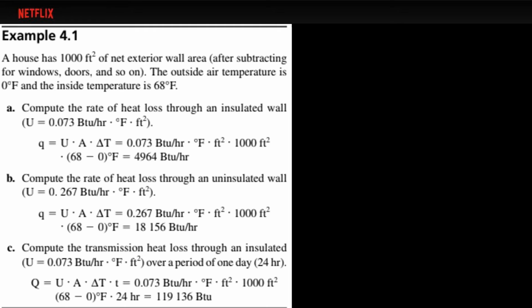So, example, a house has 1,000 feet squared of net exterior wall area, after subtracting the windows, doors, and so on. The outside air temperature is 0 Fahrenheit and the inside temperature is 68 Fahrenheit. So A, compute the rate of heat loss through the insulated wall. So now, the formula from earlier is on the last slide. It's just U times A times delta T. So 0.073 BTU per hour times Fahrenheit feet, and 1,000 feet squared. So this is the answer: 4,964 BTU per hour.